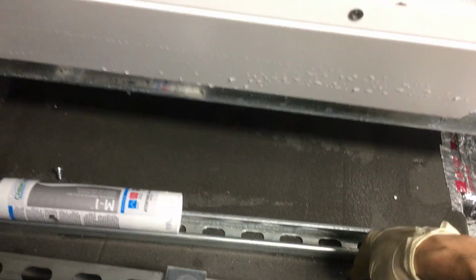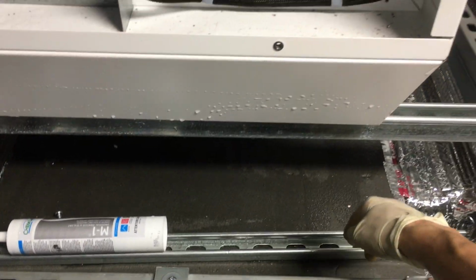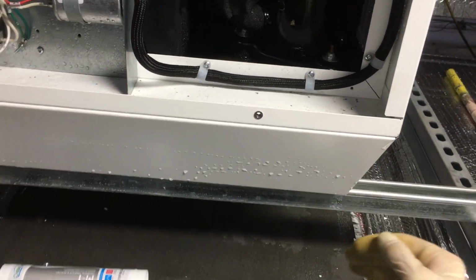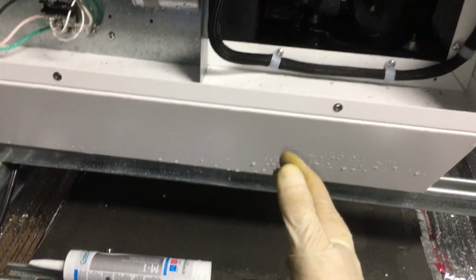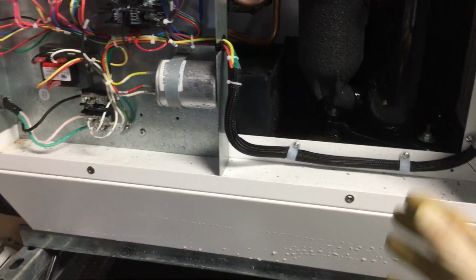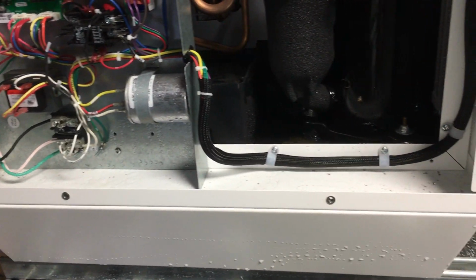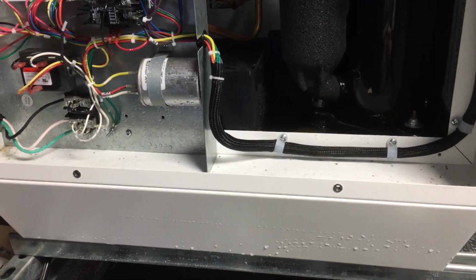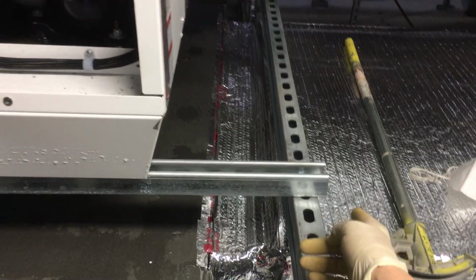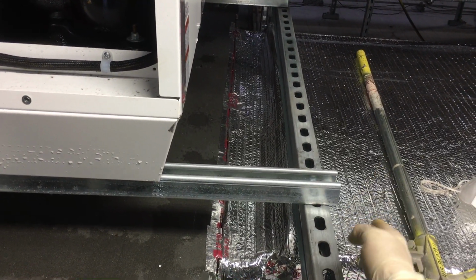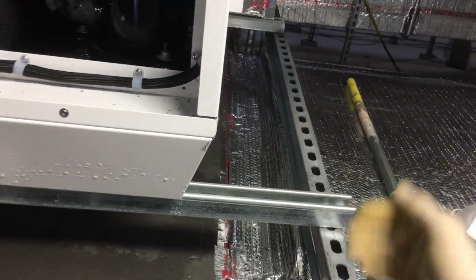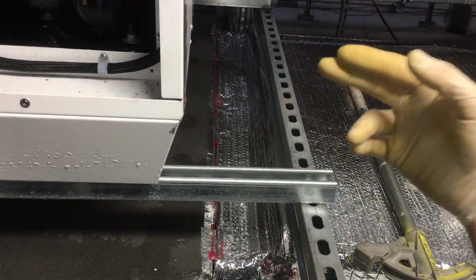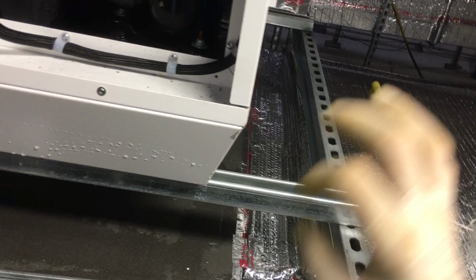And for every air handler, there's 6 air handlers in this room, a mixture of 8 ton and 6 tons, we're literally measuring every gallon of water that comes from the air handlers during normal daytime full load application, so we know exactly how many pounds of water has to be calculated to figure out the size of the reheat coil that we need, to calculate how many gallons of water need to go through that coil per hour, what the flow rate is, the size of the pump, the electrical consumption, and everything like that.